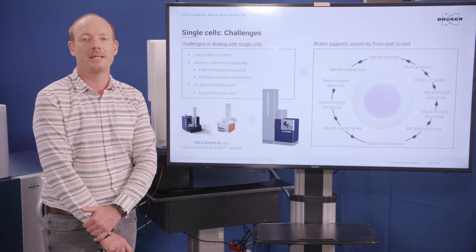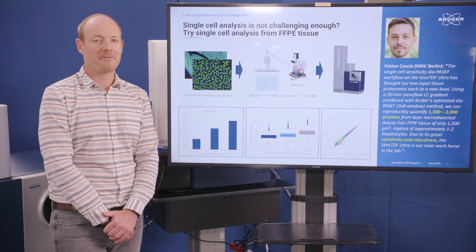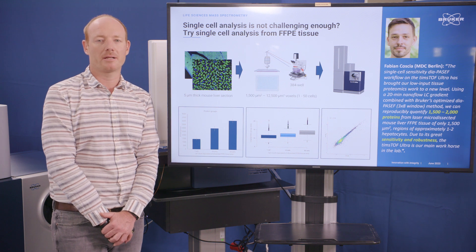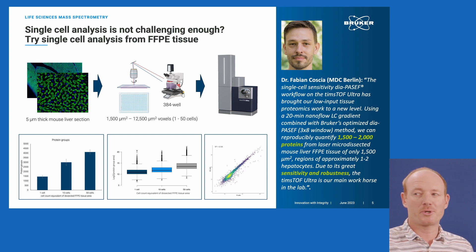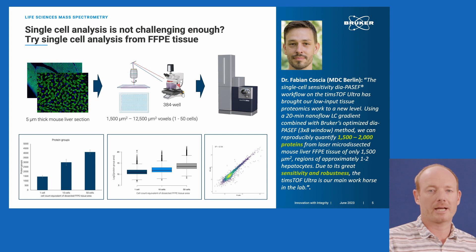The timsTOF Ultra gives us the sensitivity we need to go to the single-cell level and even beyond. We received feedback from early adopters, including Fabian Coscia, a researcher at the Max Delbruck Center in Berlin. He assessed the sensitivity using FFPE-fixed mouse liver tissue sections, using laser-capture microdissection to cut out very small pieces mimicking material from a single cell, 10 cells, or 50 cells. With just an 11-minute active gradient, this led to the identification of close to 1,500 proteins from the equivalent of a single cell, and up to 4,000 proteins from the equivalent of 50 cells.